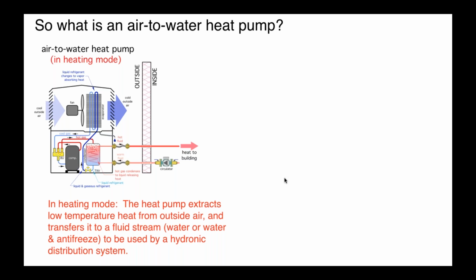Our evaporator portion of the refrigeration system is taking cold outside air, and it might be air literally at 0 degrees Fahrenheit or even colder. And we're extracting heat from that. And some people wonder, how do you get heat out of 0 degree Fahrenheit air? Well, if you take 0 degree Fahrenheit air and cool it to -15 Fahrenheit, you've extracted heat from it. Now, granted, that's very low-grade heat from the standpoint of using it for a practical application, but that's the beauty of a heat pump. What a heat pump does is essentially take low-grade heat and pump it to higher-grade heat, higher temperatures that we can use. And that's what's going on with the refrigeration system.